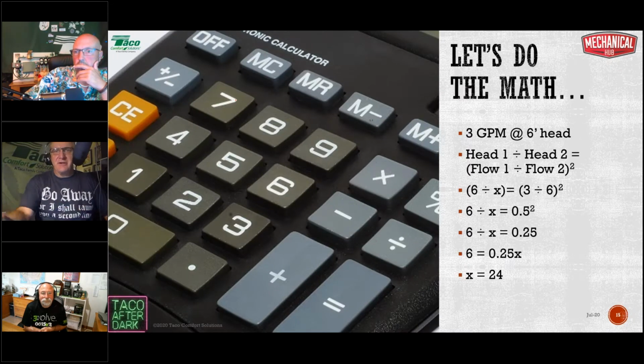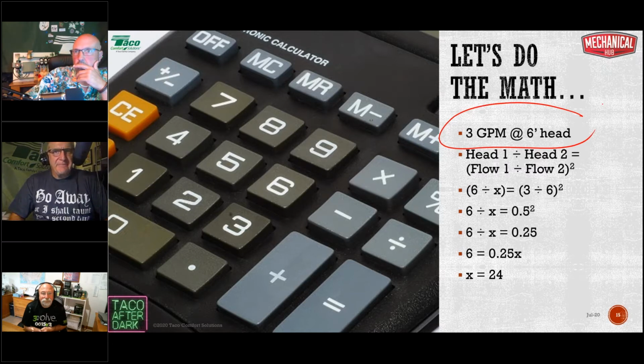Let's say I've got a zone here, and I did the math, and my 3 gallons a minute is at 6 feet of head. To plot out different points on our system curve, we use head 1 divided by head 2. Head 1 we know is 6 feet of head, head 2 is X, that's what we're trying to find. Back to 6th grade algebra: flow 1 we know is 3 gallons a minute, flow 2 we can put in whatever number we want. So head 1 divided by head 2 equals flow 1 divided by flow 2, squared.